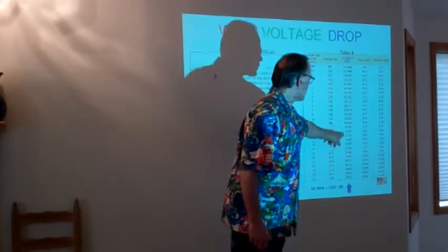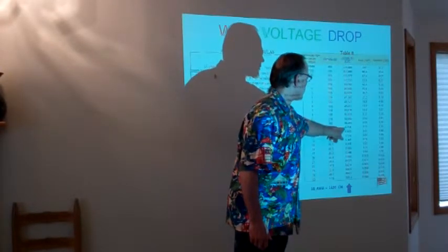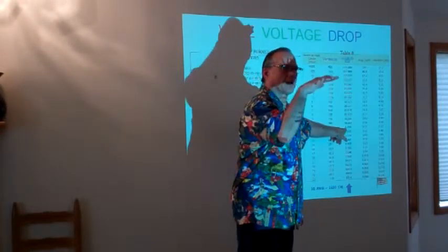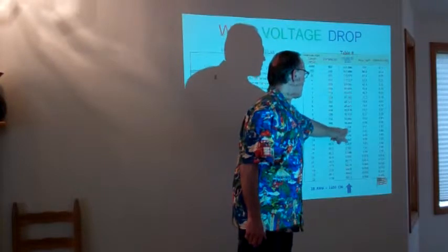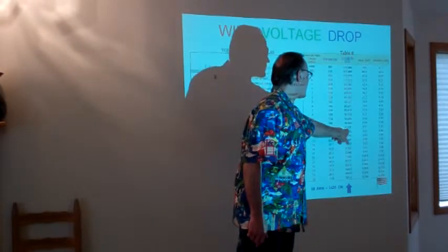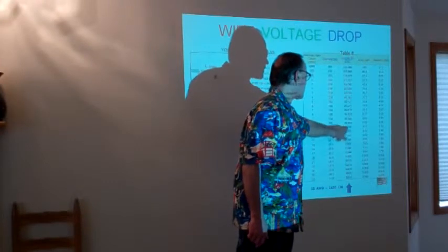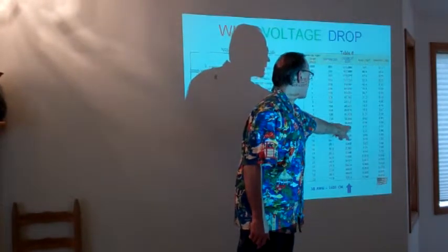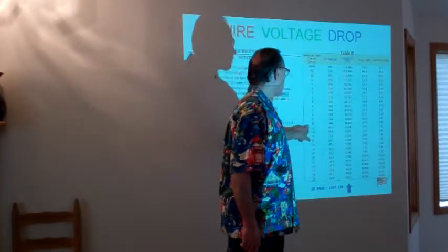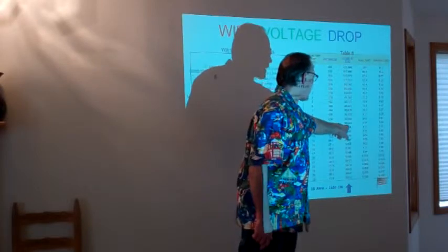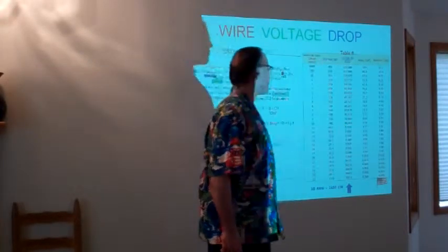What we have to do is take that number and find the closest one we have that's not below it, but above it. So what we would see here, this one right here is 8,234. We would need to go up to the next level because we fall in between at 8,600 something, to the next level of our normal wire size, which would be number 10. It's at 10,383 circular mils.